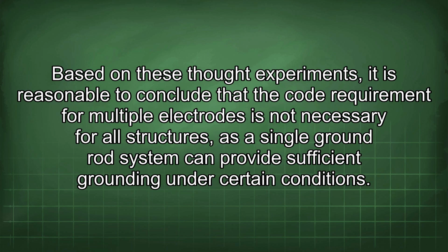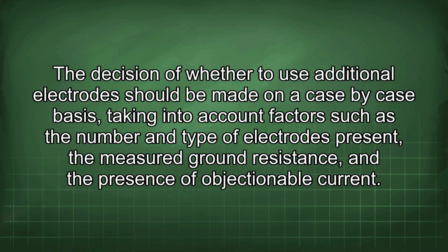Based on these thought experiments, it is reasonable to conclude that the code requirement for multiple electrodes is not necessary for all structures, as a single ground rod system can provide sufficient grounding under certain conditions. The decision of whether to use additional electrodes should be made on a case-by-case basis, taking into account factors such as the number and type of electrodes present, the measured ground resistance, and the presence of objectionable current.